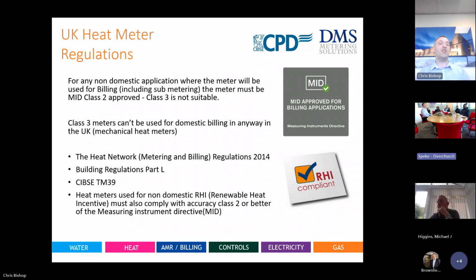So some UK regulations relate to a term called MID Class 2 or Class 3. So if we go back before 2014, before the district heating and billing regulations started off, there was acceptable use for either a Class 2 meter, which is obviously more quality or more accuracy compared to a Class 3. The difference between Class 2 and Class 3: Class 2 is no moving parts, highly sensitive, covers minimum flow rates, can be repaired and recalibrated long term.